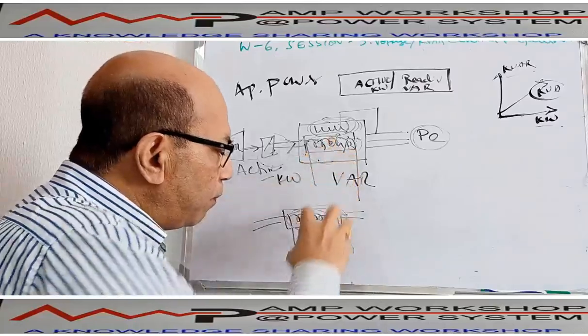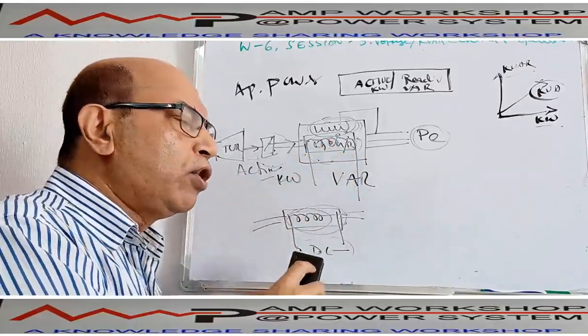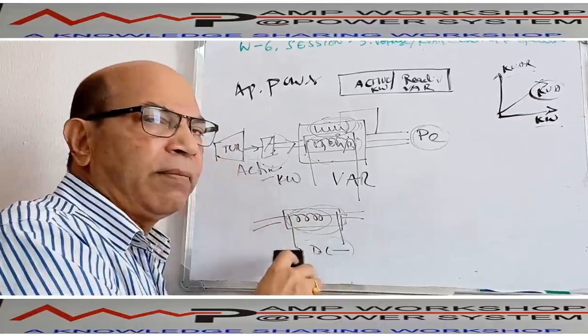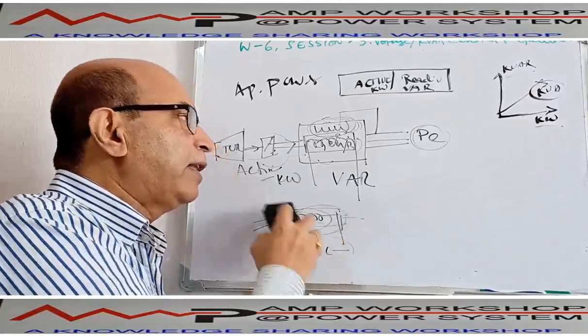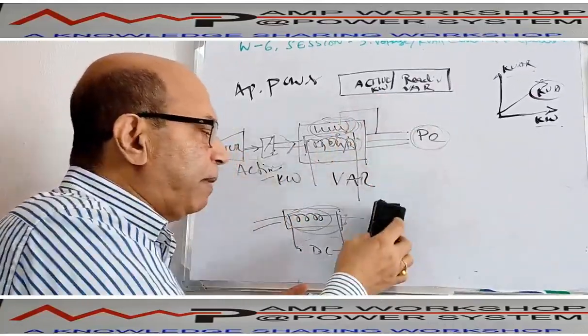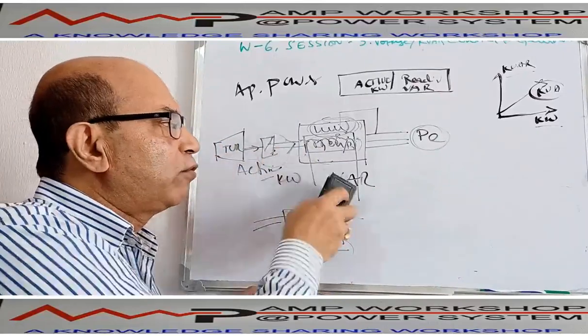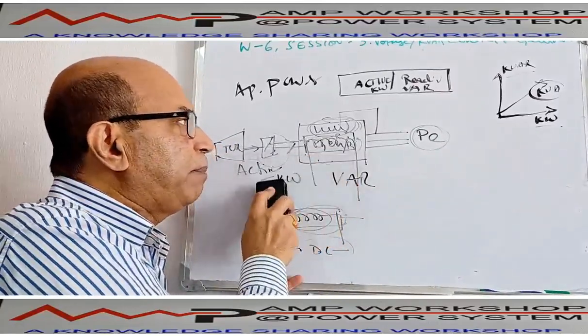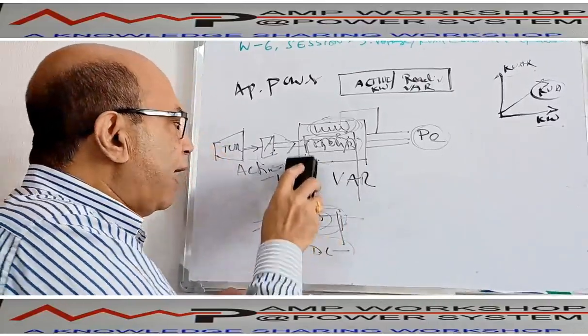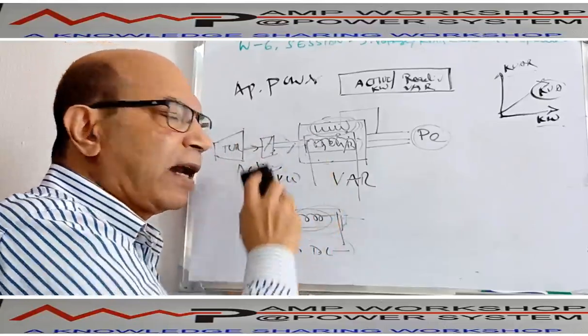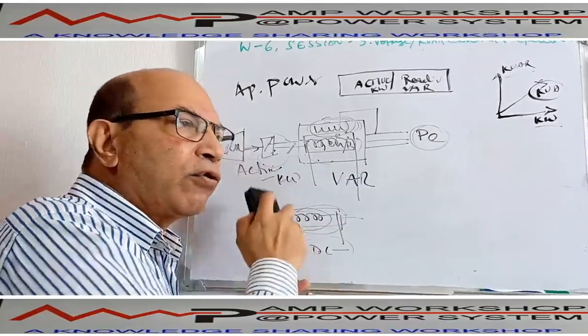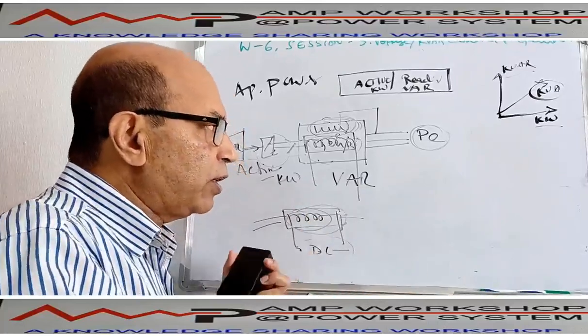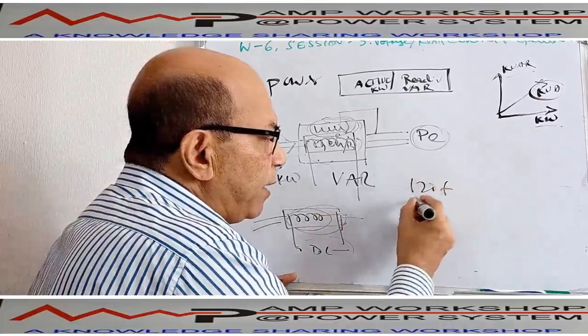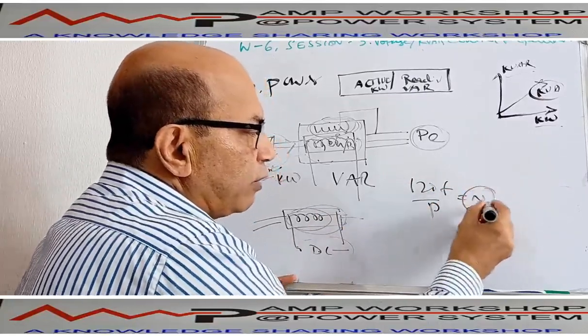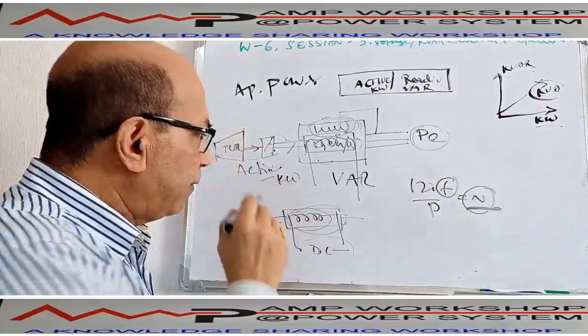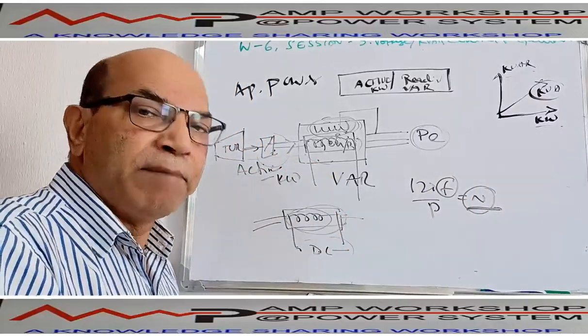The DC current which is flowing through the rotor, we call excitation. When the rotor is excited by DC current, the rotor is converted to a magnet, and that magnet is responsible for producing this reactive power. So when we look into the generator, we can see there are two parts. One part is responsible for the active power, another part is responsible for the reactive power. Who is responsible for the active power? That is the turbine rotation. We already discussed that rotation is indirectly producing frequency, because 120 F by P equals RPM. So when it is rotating at N RPM, it is producing a frequency of 50 Hz. That means this rotation is actually responsible for the frequency generation.